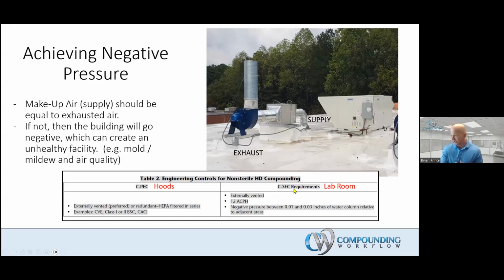That's what it says. The CSEC, the lab room must be externally vented. The translation, without it explicitly stating, is that there's no opportunity for air that has been supplied into a hazardous drug space to be recirculated back into the air handling system. It is what we call one-pass air. That is the intent of the chapter, even though it does not explicitly state it as one-pass air or no recirculation. That's what they mean by externally exhaust.